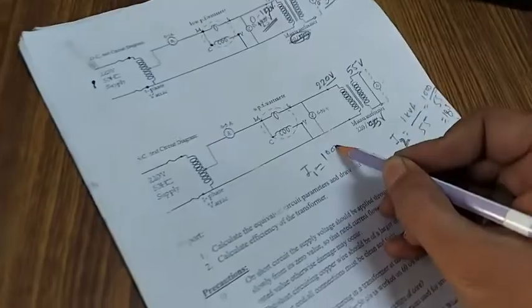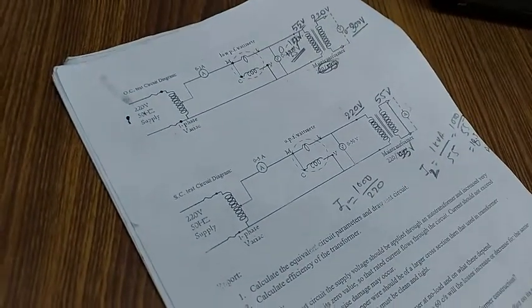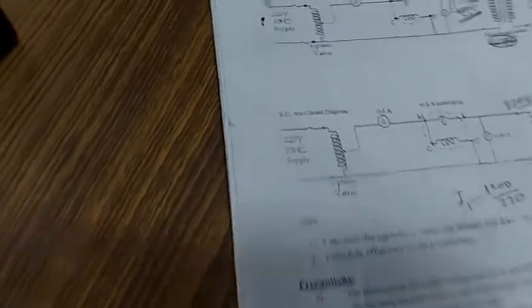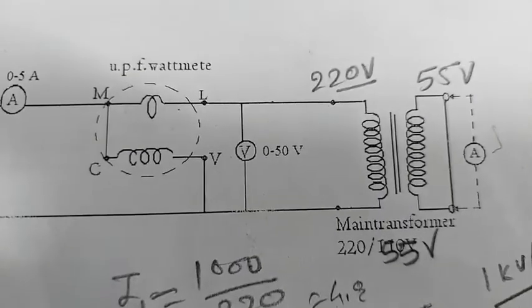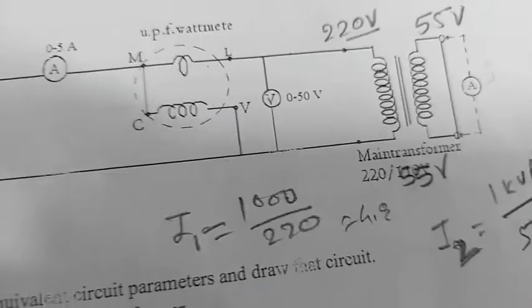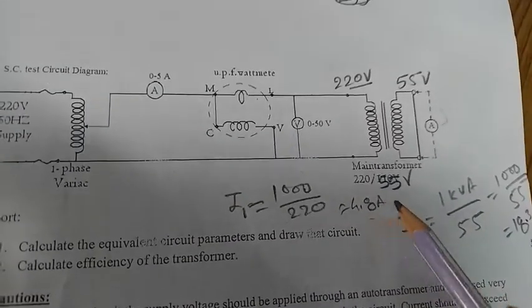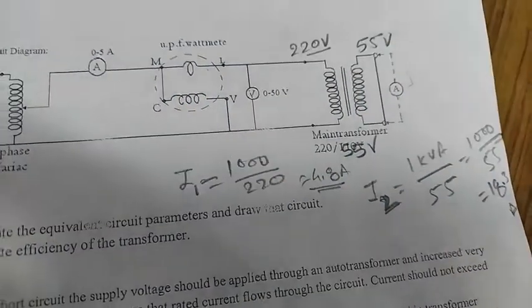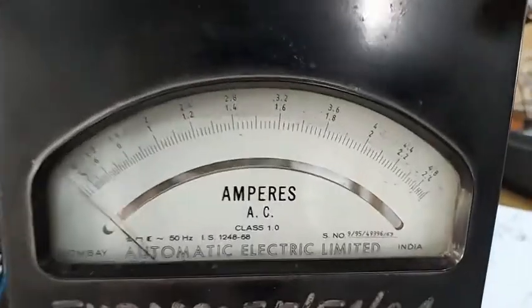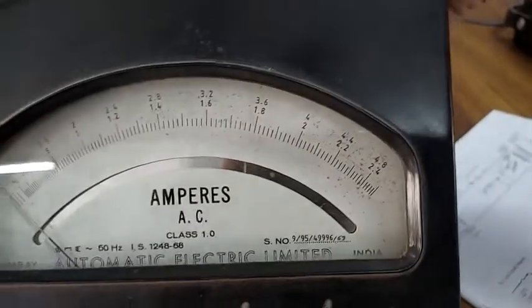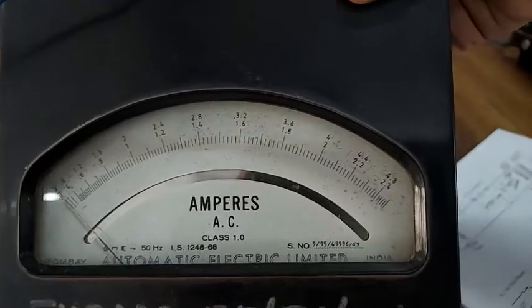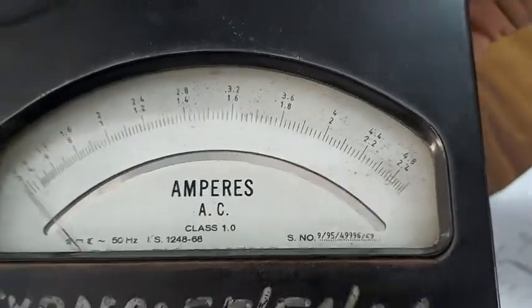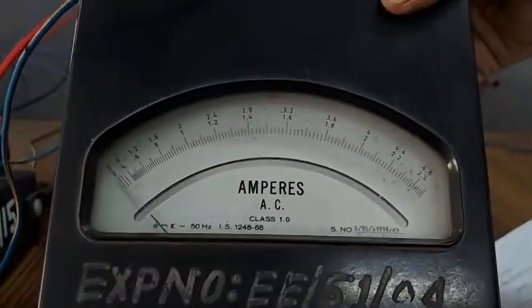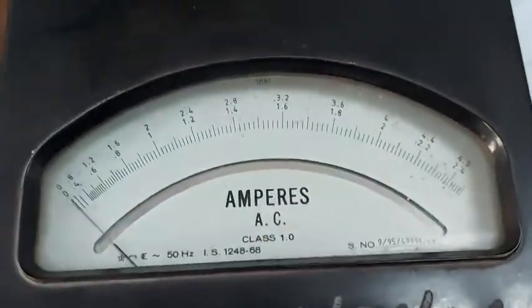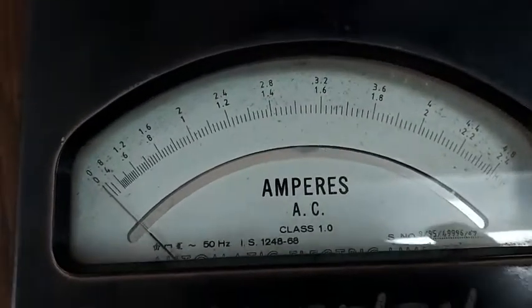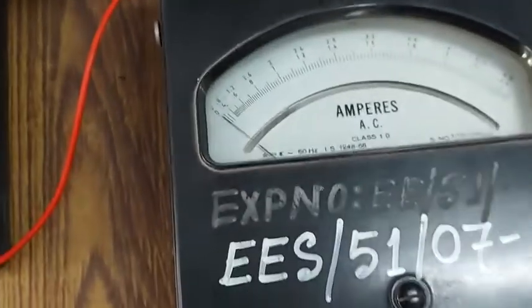It can also be calculated by dividing 1000, that is 1 kVA, by 220, because we are going to measure the current through the primary winding, which is the high voltage winding, the 220 volt side winding, and the total power is 1 kVA, so it will be 4.8, and the 5 ampere range will be suitable. So let's see how much current is coming, because if we connect a 2 ampere or 1 ampere range ammeter, it will not be suitable for reading that, because the expected value will be a little higher than that. So it is better to connect an ammeter of at least 5 ampere. So we have connected a 0 to 5 ampere ammeter.